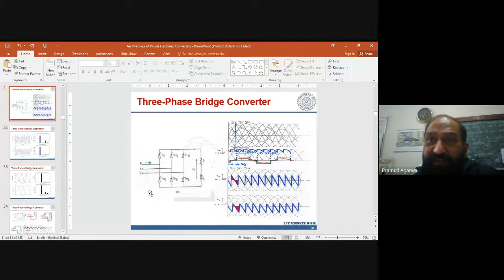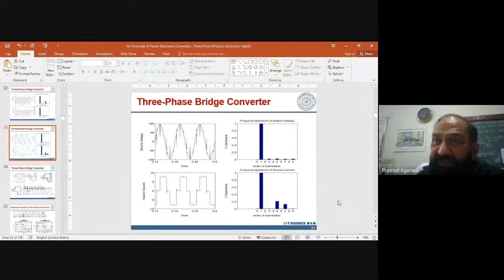As far as input current is concerned, input voltage and the current, voltage will have spikes. If you neglect these spikes, you have only the fundamental voltage. And if you see the input current, which is now quasi-square, and you do the harmonic analysis, it has fundamental, 5th, 7th, 11th, 13th, odd order harmonics other than triplens. Third harmonics are not present. You can see there is no scope of flowing of third harmonic because all the third harmonics are in phase, so there must be a return path, and which is not there. So you have only the fundamental, then 5th, 7th, then 11th, 13th, then 17th, 19th, and so on.